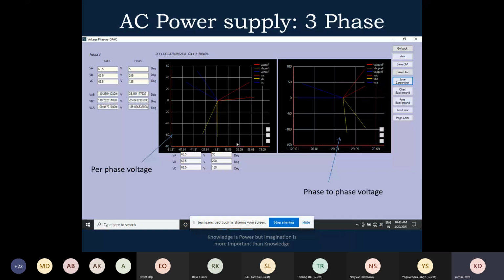Okay, so you look at it here. There is one simple example which is demonstrated here. It is 63.5 volt at 5 degrees for A phase, 63.5 volt at 245 degrees for B phase, and 63.5 volt at 125 degrees for C phase. That is called the pre-fault condition. And another condition is the abnormal condition. You look at it, it's 63.5 volt at 30 degrees, 63.5 at 270 degrees, 63.5 at 150 degrees. That is the second condition.